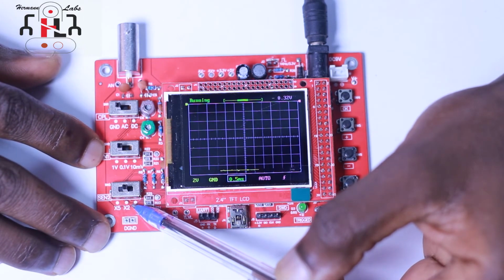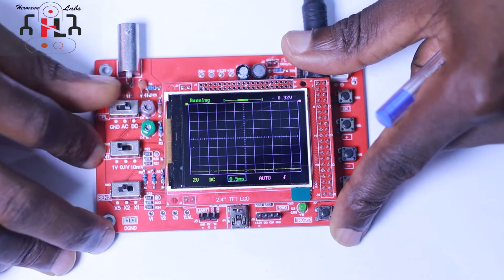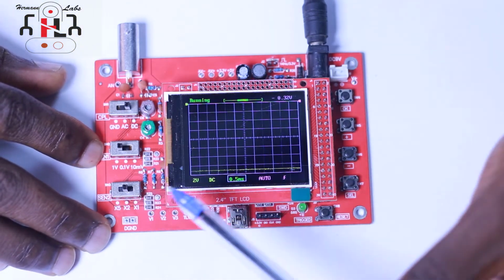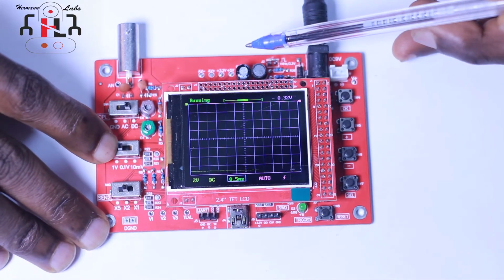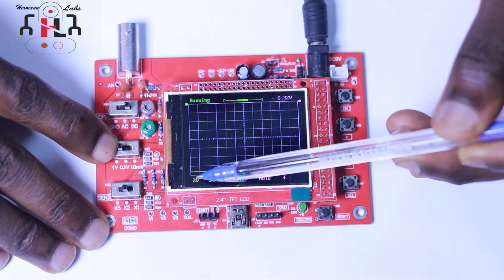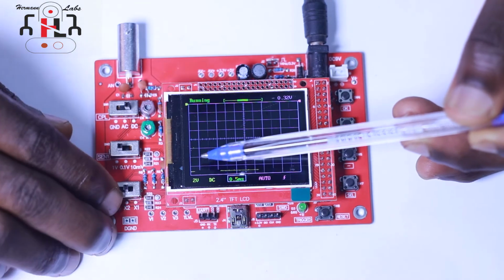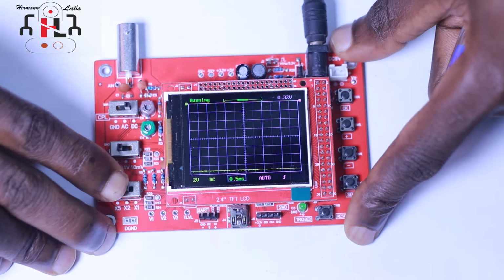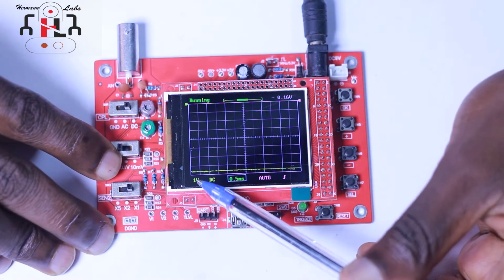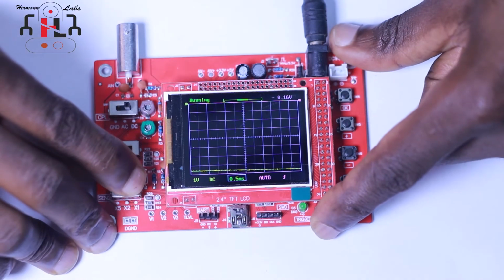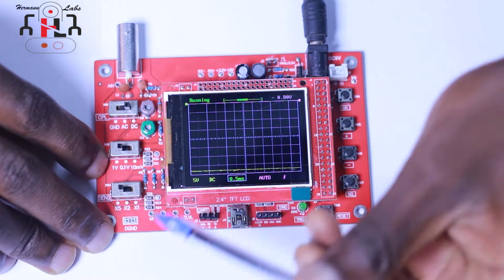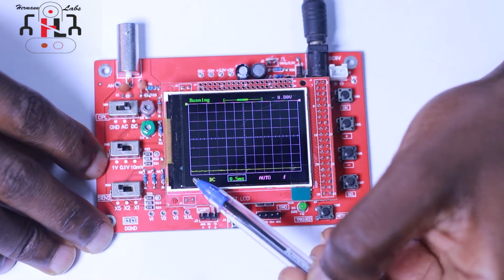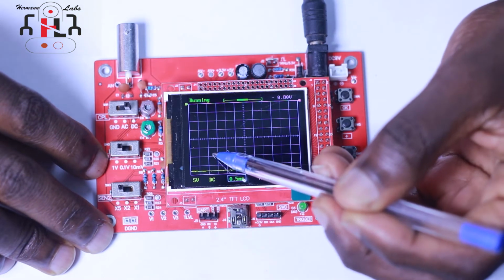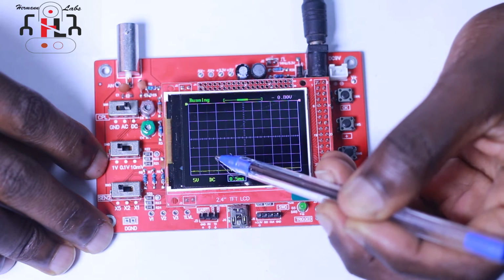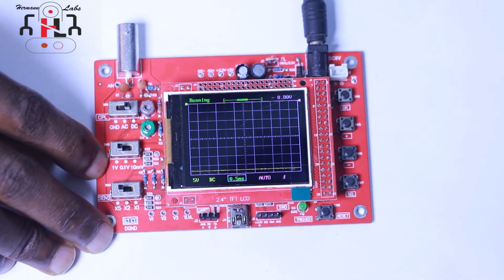Depending on the multiplier, let's go to DC: if we select 1 volt here, we see 2 volts because the multiplier is set to 2. If we set the multiplier to 1, the voltage goes to 1. If we set the multiplier to 5, the voltage goes to 5, meaning each division corresponds to 5 volts.